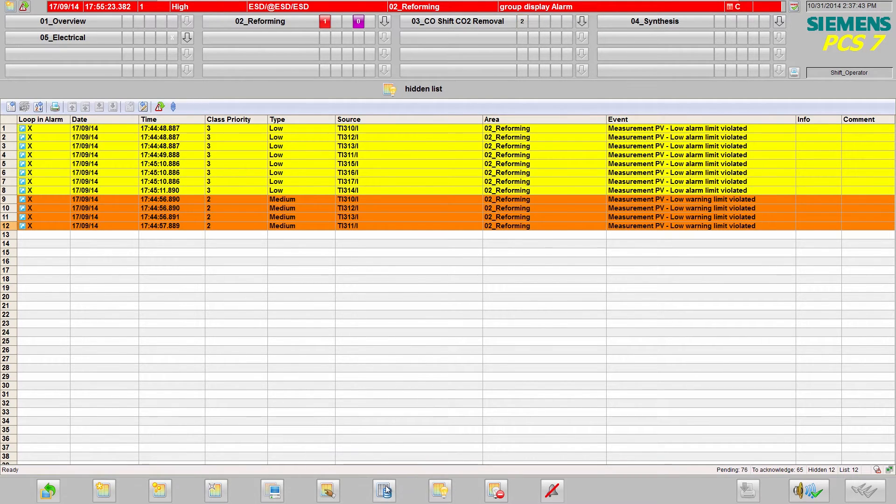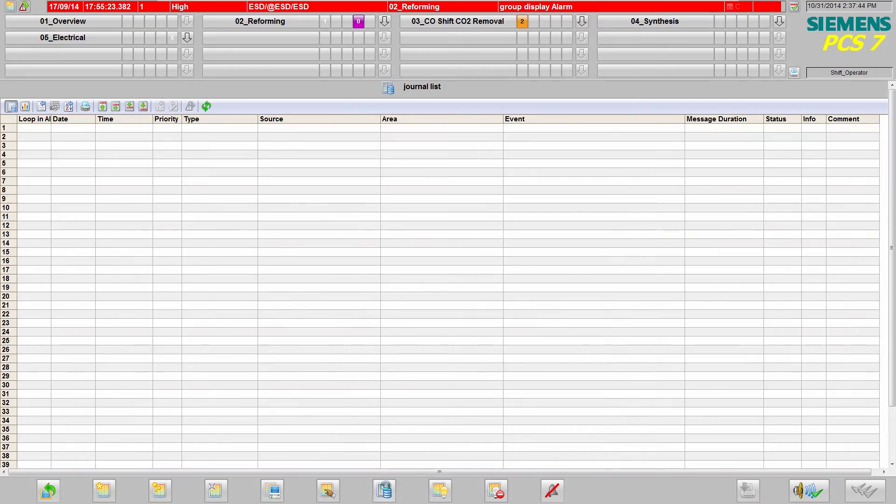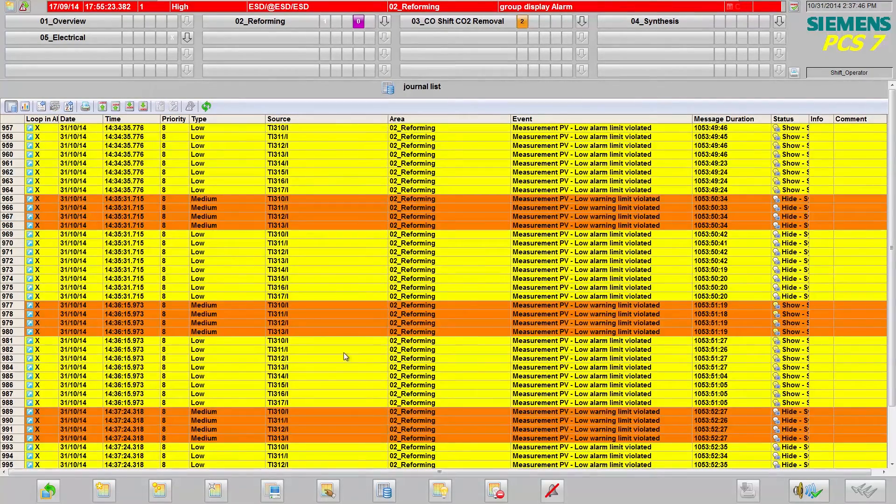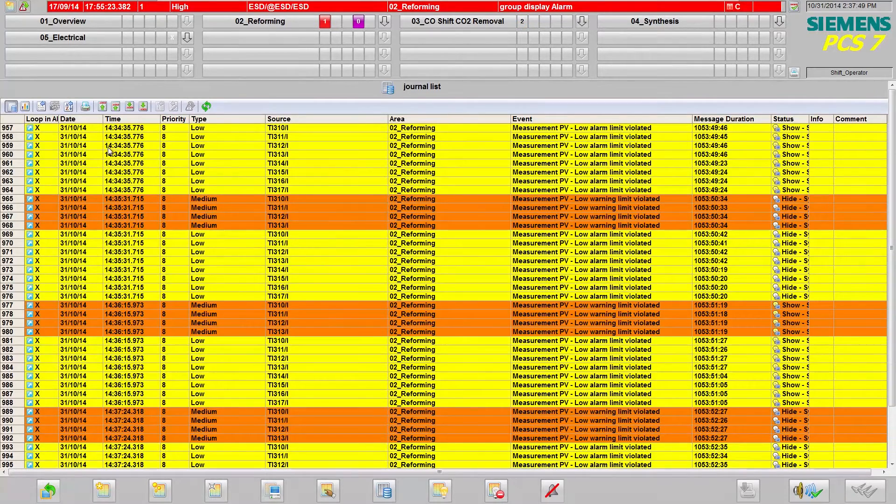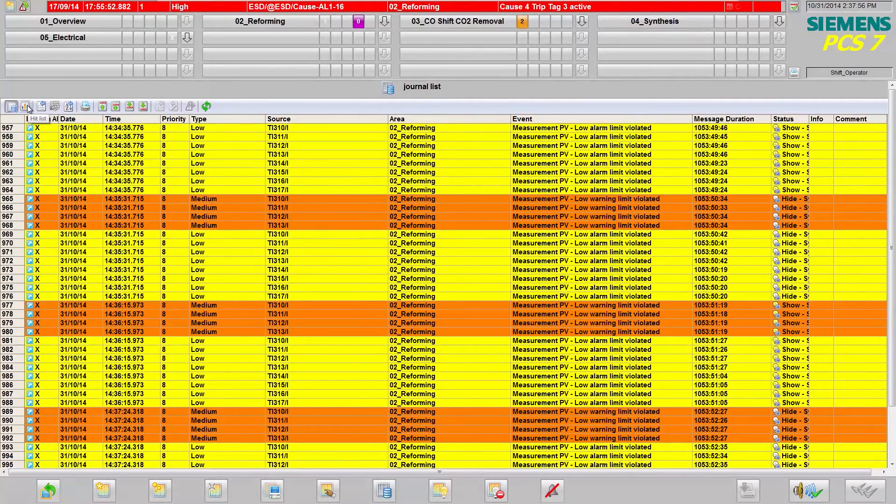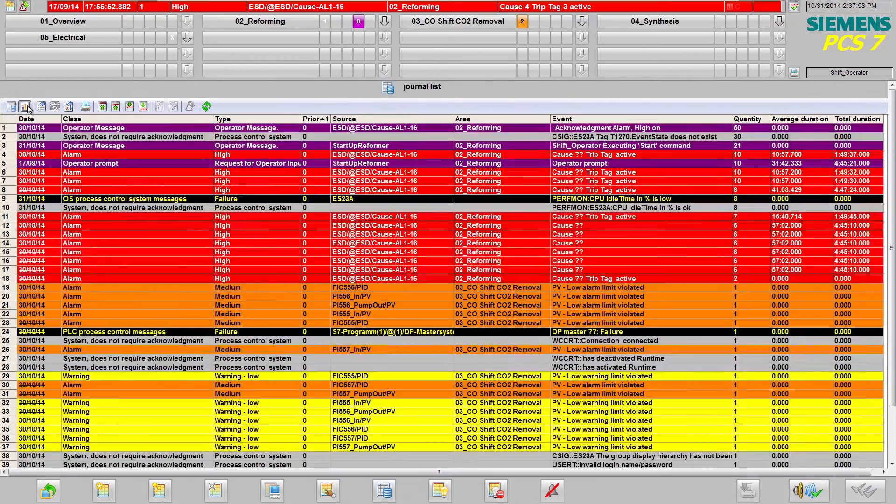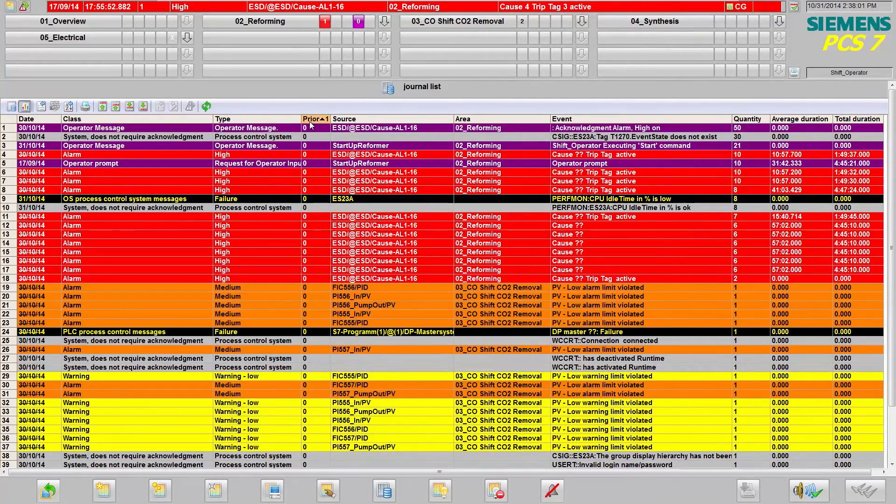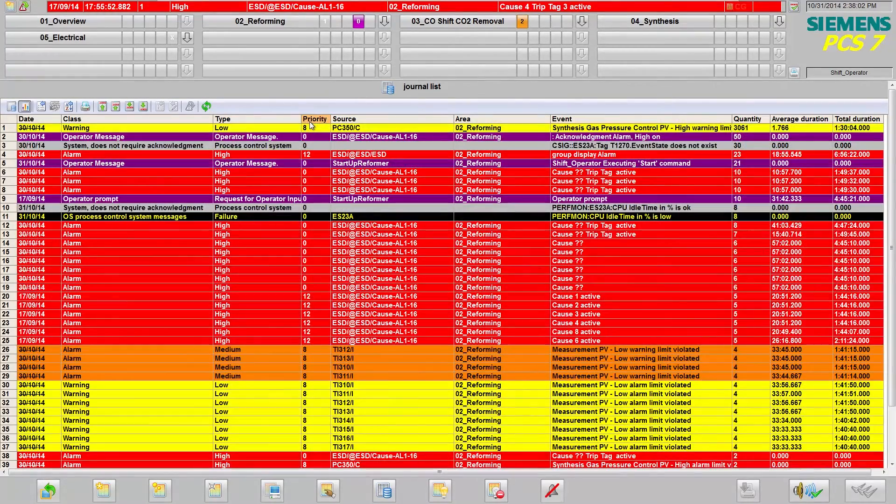Another possibility for optimizing the alarm system is statistical evaluation of the alarms. To do this, I am switching to the journal list where all the messages in the archive are displayed. From the upper bar, I can navigate to the hit list, which displays messages according to statistical criteria.